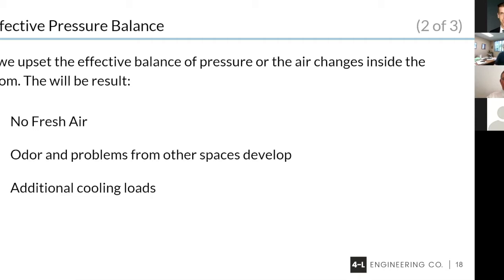If you close it off, your unit becomes depressurized relative to the people on your left or your right that may have their outside air damper open, or the person above you in the upstairs unit, or the one in the downstairs unit. Everybody needs to stay at a fair pressure balance inside these buildings so that if a person has a problem in a center unit, he doesn't distribute it. If he's at a negative pressure and he doesn't have the disease and the person next door that's pressurized has it, it's going to migrate from the higher pressure to the lower pressure.